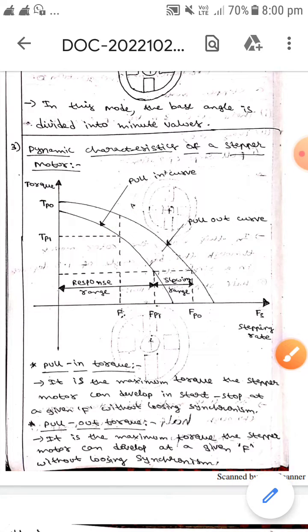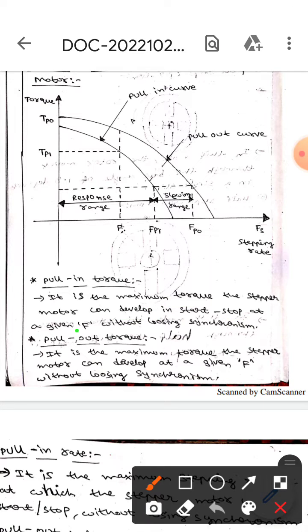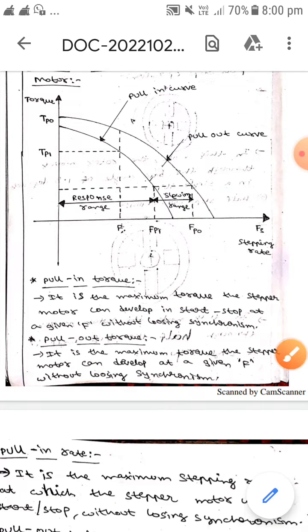Whereas this one is the response range. The first term is pull-in torque, which means it is the maximum torque the stepper motor can develop to start or stop at a given stepping rate without losing synchronism. The next one is pull-out torque, which means it is the maximum torque the stepper motor can develop at a given stepping rate without losing synchronism.